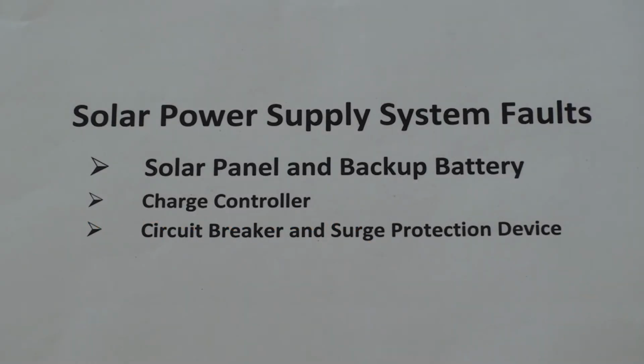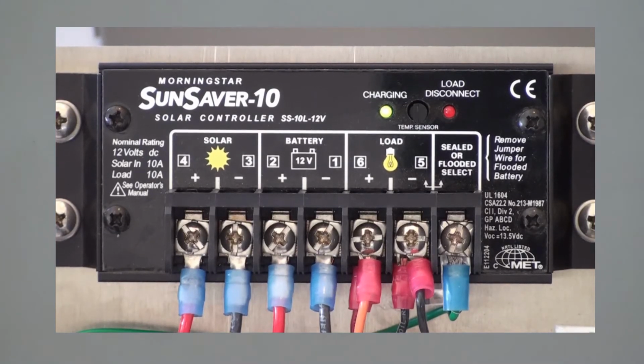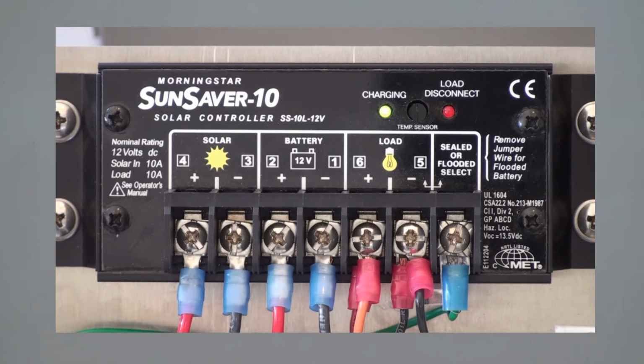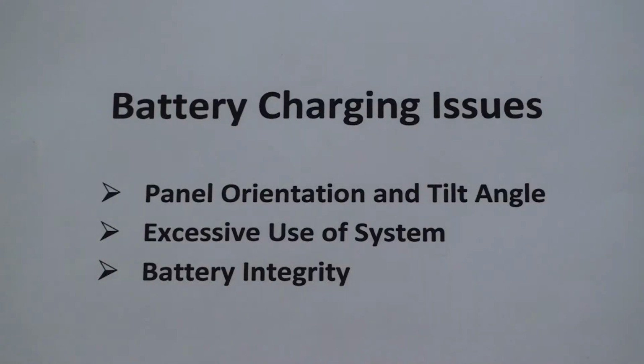The first fault area we're going to look at is the solar panel together with the backup battery. There are cases where the voltage is measured on the solar input to the charge controller, but the battery is not being charged properly, as evidenced by a low voltage disconnect or intermittent operation of the system. These conditions can be caused by improper panel orientation and tilt angle, excessive use of the system, or battery integrity.